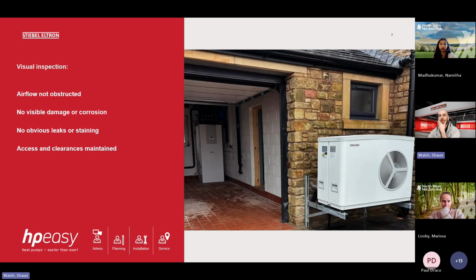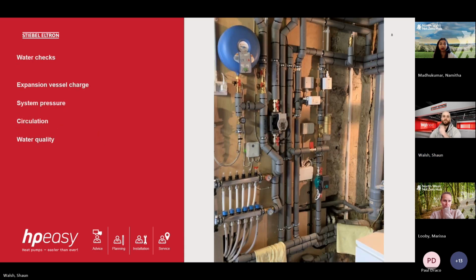Okay. And most of the issues that you will come across are quite evident. You'll be able to see them without having to go too deep into any controllers or commissioning settings. If something's not right, normally you will see it first. Okay. One of the big important things when it comes to servicing heat pumps in general is water quality. Water quality is massively important for an air source heat pump or any heat pump. Water quality protects the heat exchanger of the heat pump. If water quality is poor, the heat exchanger can get blocked up, and that can cause performance issues with the machine.